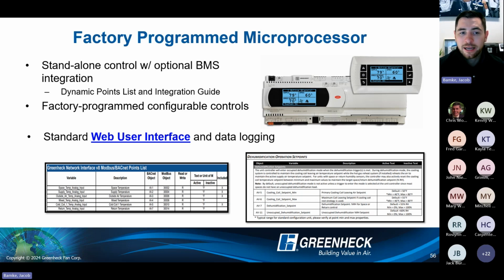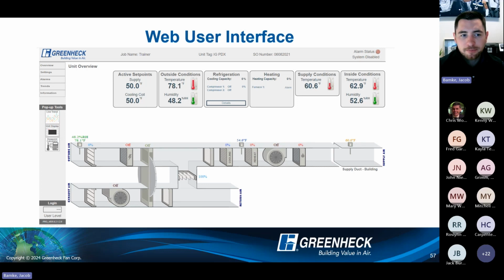And then lastly, we have a standard web user interface. So anytime that you get a microprocessor, basically you will have the ability to take an Ethernet cable, run it down to the building network, and connect to this web user interface. When you're connected, you just punch in an IP address while you're on that building network, and you can see how this unit operates. Up in the upper left, you can see I have a settings tab, which shows me the main settings of that controller. The alarms tab gives me the ability to look at all of my alarms historically. I can see some trend data, and then the unit display actually gives me the ability to act as if I had a remote mounted display for that controller. So it's a direct mimic of that microprocessor screen. All controllers come with a built-in LCD display, but one main benefit is that you get that remote mounted display.